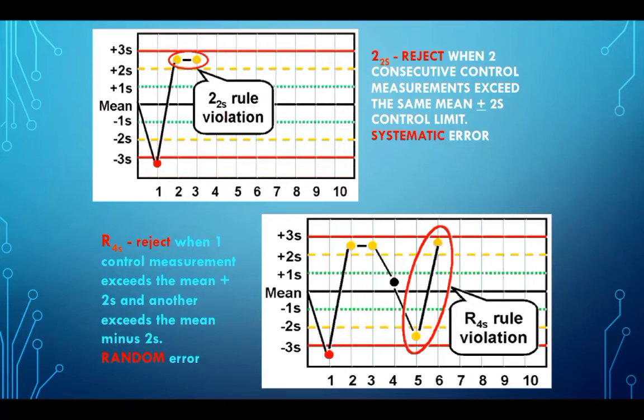Don't run patient samples, stop testing, do the root cause analysis, take appropriate action, after that run control again, and reject both of these values in the calculation of your monthly mean and SD. Use only the accepted values. This understanding of statistical concepts is very important. These calculations are provided to you by your machines. We discuss certain formulas and that graph for our understanding. What is more important is which variation is significant. We have to detect that.